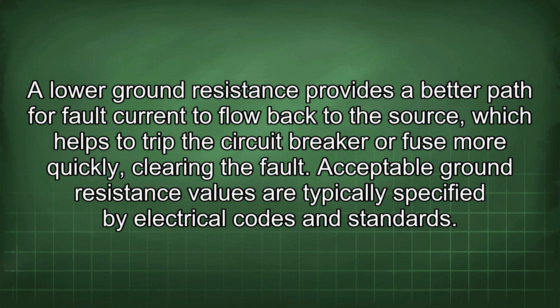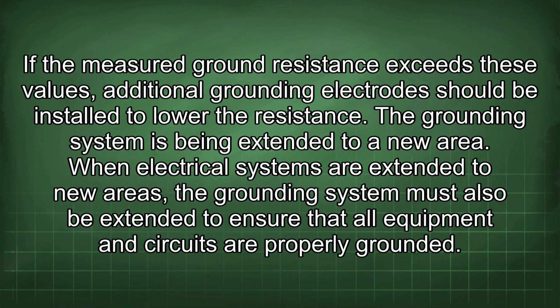Acceptable ground resistance values are typically specified by electrical codes and standards. If the measured ground resistance exceeds these values, additional grounding electrodes should be installed to lower the resistance. The grounding system is being extended to a new area. When electrical systems are extended to new areas, the grounding system must also be extended to ensure that all equipment and circuits are properly grounded.